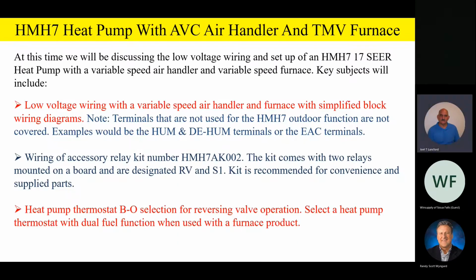Okay, so this time let's go ahead and look at that low voltage wiring of an HMH7 heat pump with a variable speed air handler and a variable speed furnace. And just like we did before, guys, we're going to be looking at a simplified block wiring diagram and looking at it, wire for wire. Now, one thing I'd ask you to please note is that the terminals that are not being used for the HMH7 outdoor function are not going to be covered.